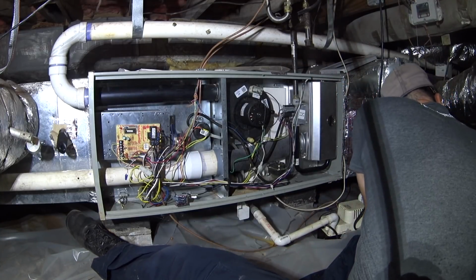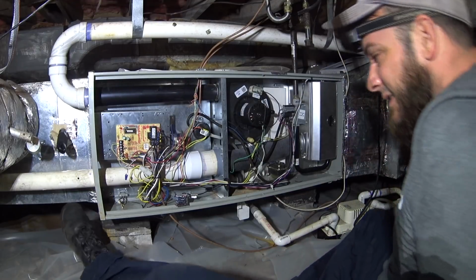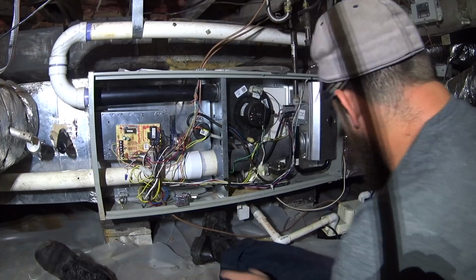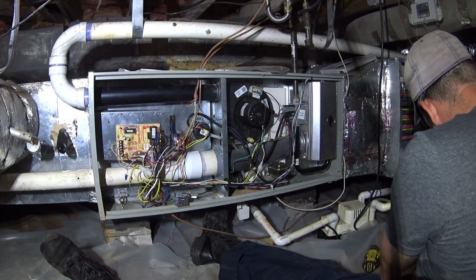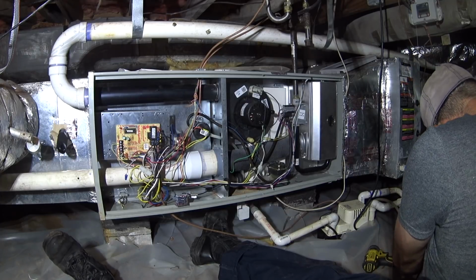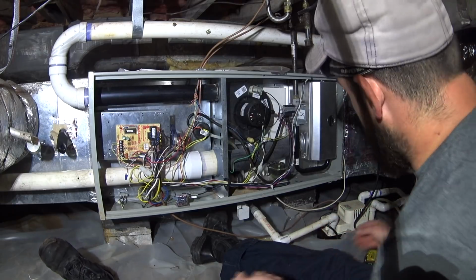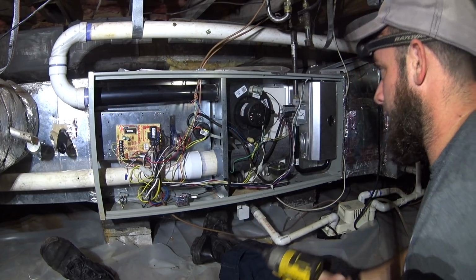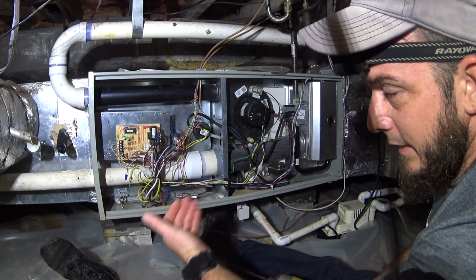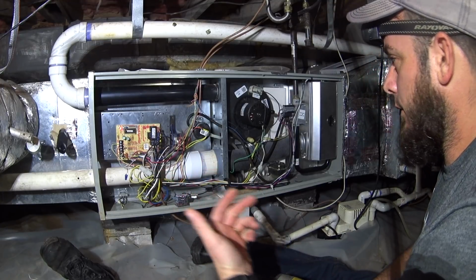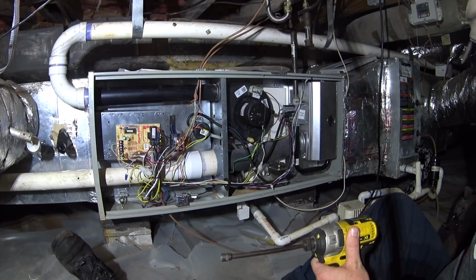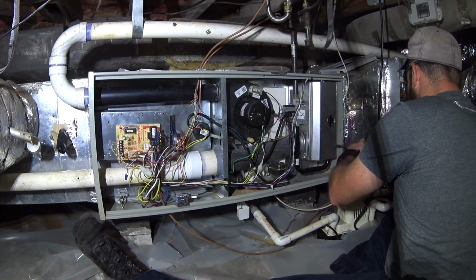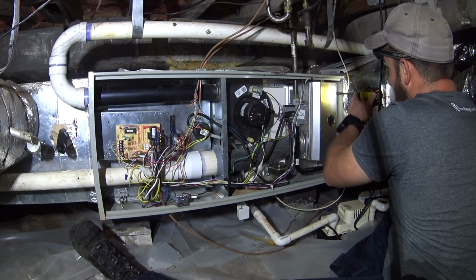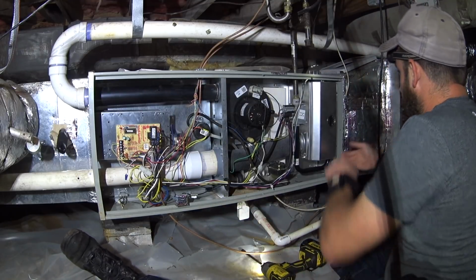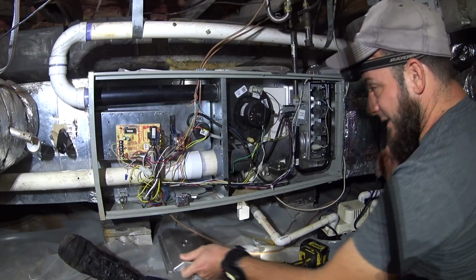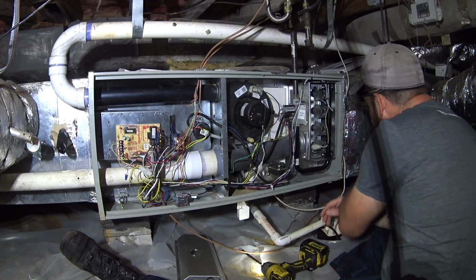And so, as much as I don't like to, since I didn't set this system up, I would generally not relocate that capacitor until there seems to be some need for it. If the blower quits, then obviously there would be a need to get to that capacitor, and at that point, if I were to replace the capacitor, I would actually bring it to the front of this panel. And I know that I've had commentary regarding the fact that that's not a great idea, because then you destroy the UL listing of the system. But when you think that that capacitor should be checked and it's not accessible, most people are going to not check it.